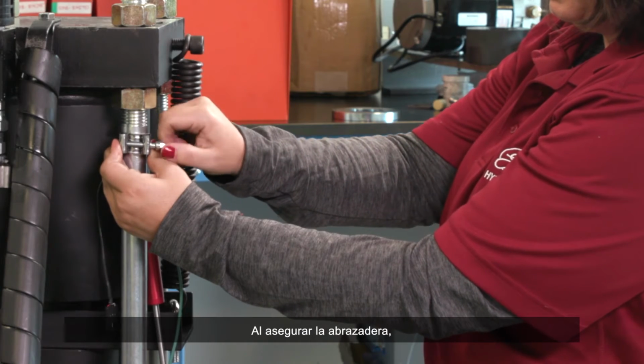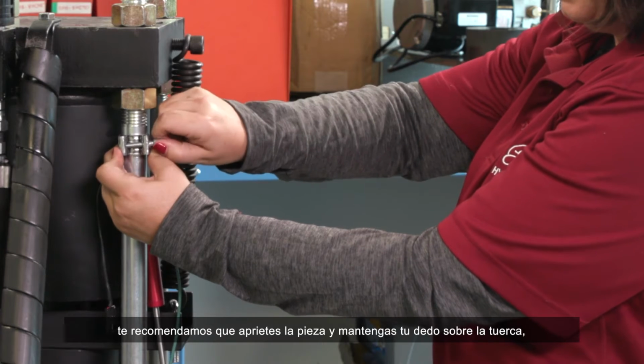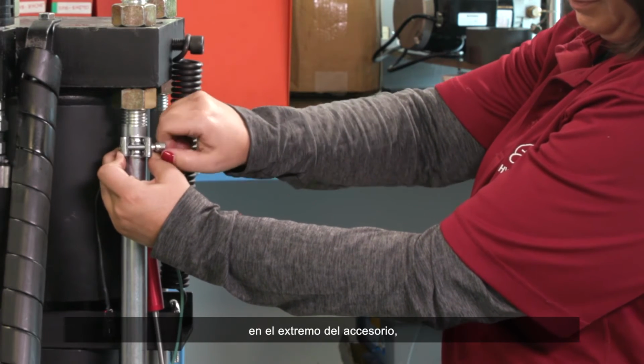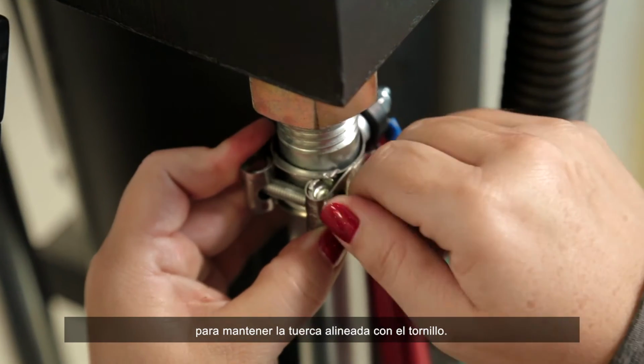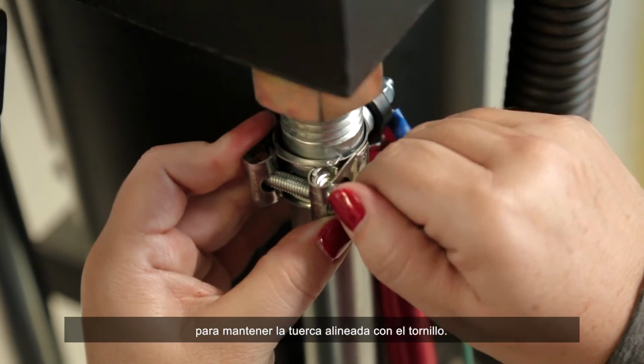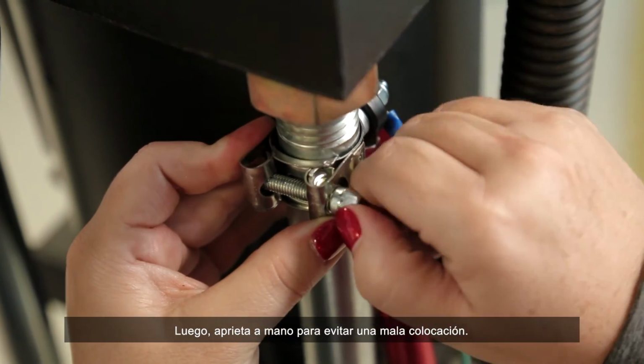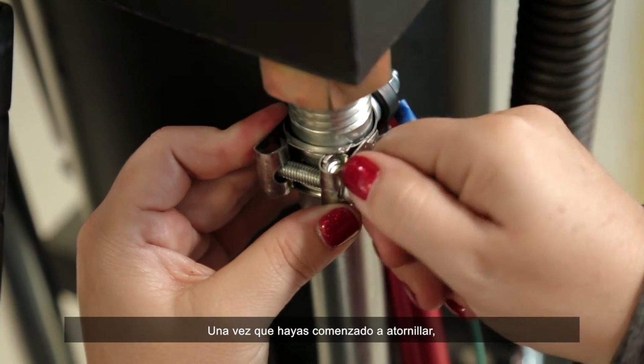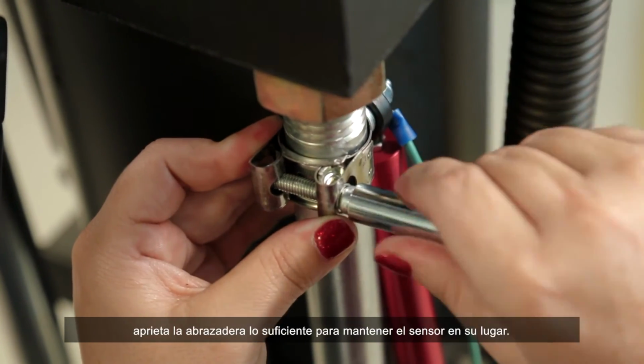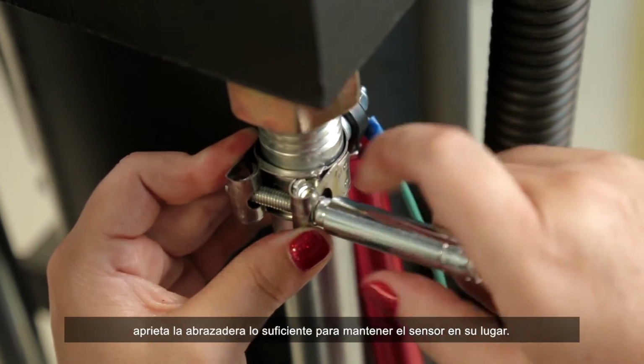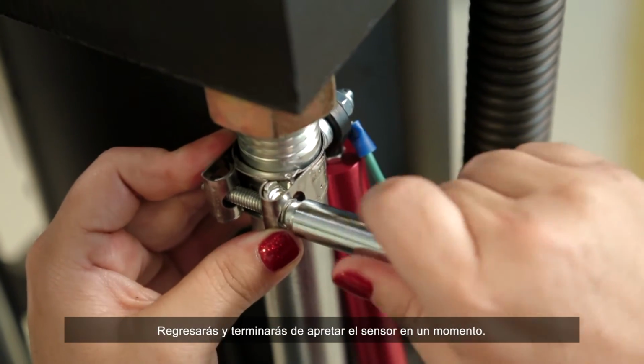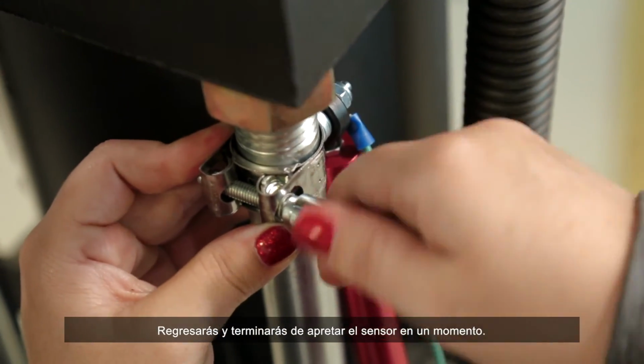When securing the clamp, we recommend that you pinch the clamp and hold your finger over the nut on the attachment end to keep the nut square with the screw. Then hand tighten to avoid cross-threading. Once you have the thread started, tighten down the clamp just enough to hold the sensor in place. You'll go back and finish tightening the sensor in a minute.